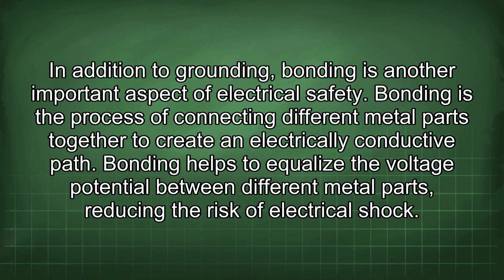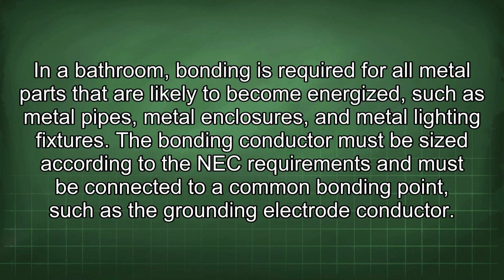In addition to grounding, bonding is another important aspect of electrical safety. Bonding is the process of connecting different metal parts together to create an electrically conductive path. Bonding helps to equalize the voltage potential between different metal parts, reducing the risk of electrical shock. In a bathroom, bonding is required for all metal parts that are likely to become energized, such as metal pipes, metal enclosures, and metal lighting fixtures.